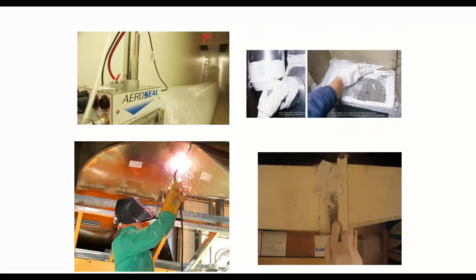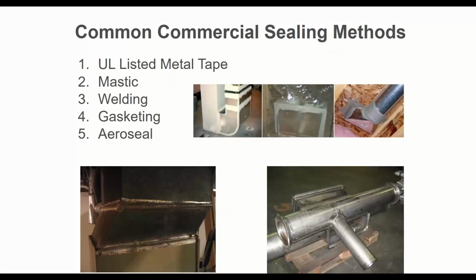You can gasket it. I don't think I had a picture of that. I didn't. You can gasket it, but that means you're going to take the two pieces of duct and they're going to fit together like this, and you're going to put gasketing material on that flange. And then when you put it together, you're going to screw them together, and that gasket's going to compress, and that's going to be your seal.